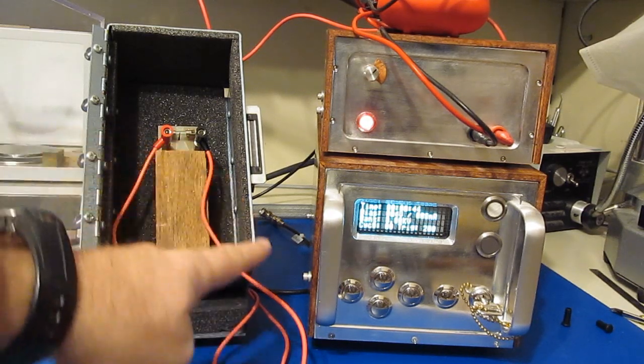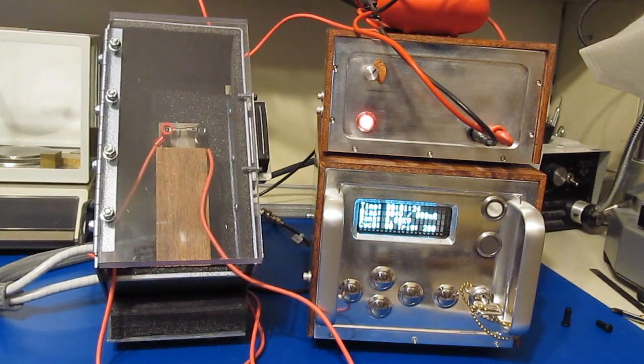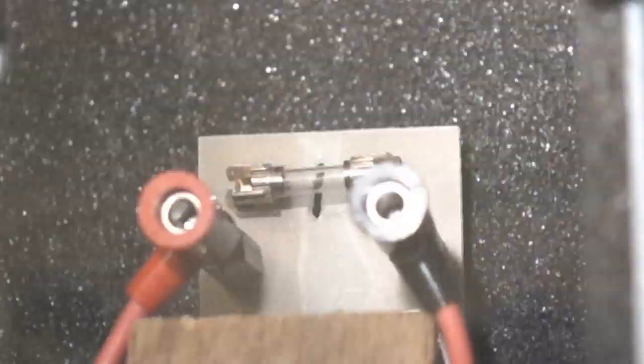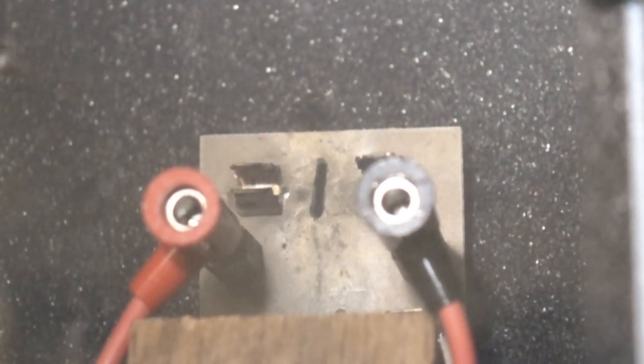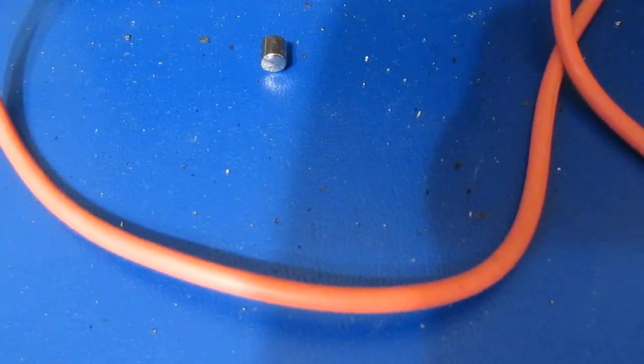As you can see, I've gone ahead and I've connected our small fuse block up here to our transient generator. I'll go ahead and apply a single transient off this generator and we can see if we can capture this with the camera. You can see there's basically nothing left of that fuse - a few fragments here, a little bit of dust, that's about it. And just see how the end of that fuse is buckled - a lot of pressure.